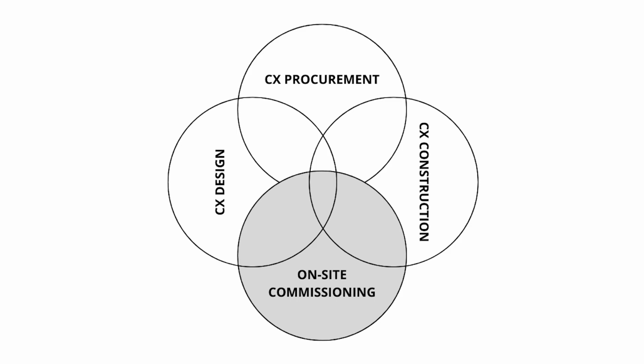On-site commissioning: when commissioning is integrated into procurement, design, and construction processes, you'll have equipment arriving at site that has been properly tested in the factory, there are far less design issues in the field, and you'll have a smooth handover from construction to commissioning.